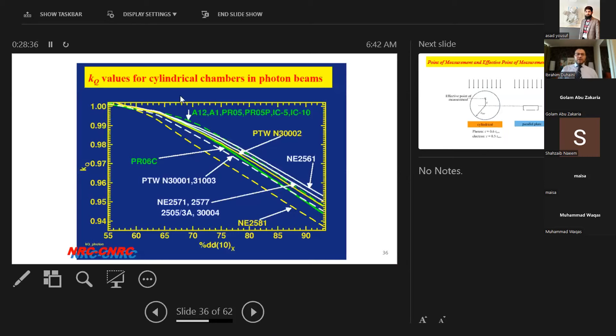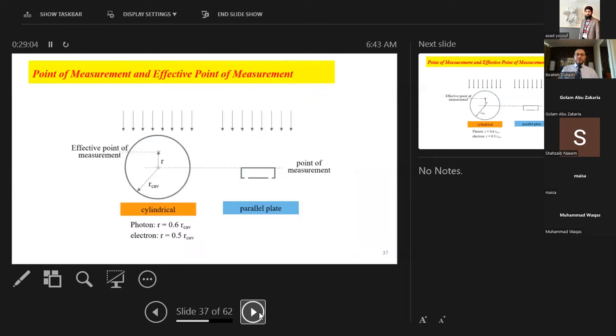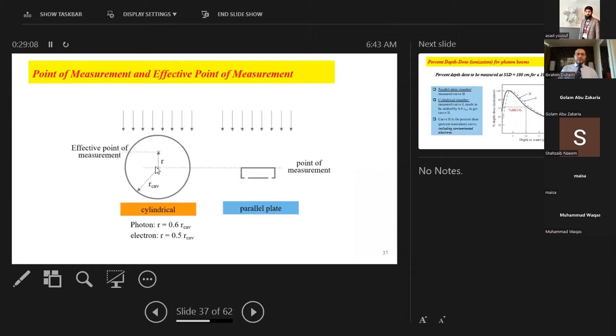kQ values for cylindrical chambers in photon beams are tabulated by chamber type and energy — you can interpolate based on percent depth dose energy. For the effective point of measurement in TG-51: cylindrical chambers for photons use 0.6 times the cavity radius; for electrons, 0.5 times the radius; for plane-parallel chambers, the measurement point is at the surface of the plate.